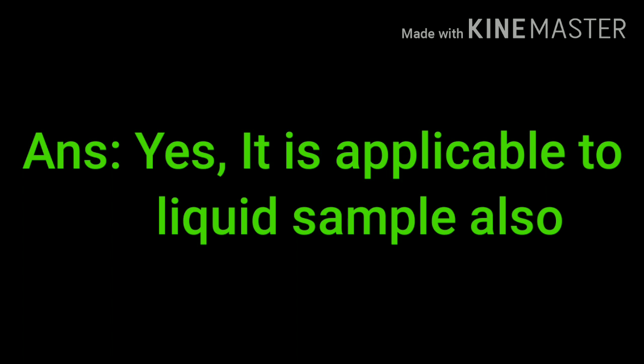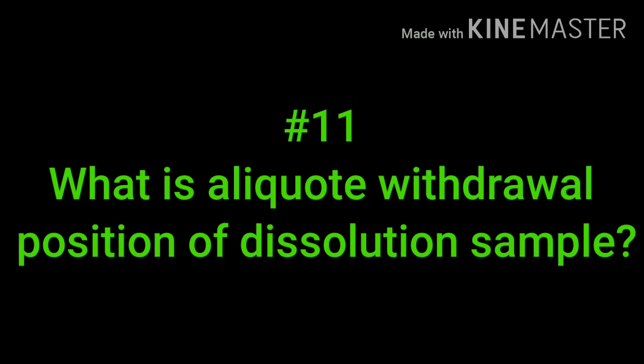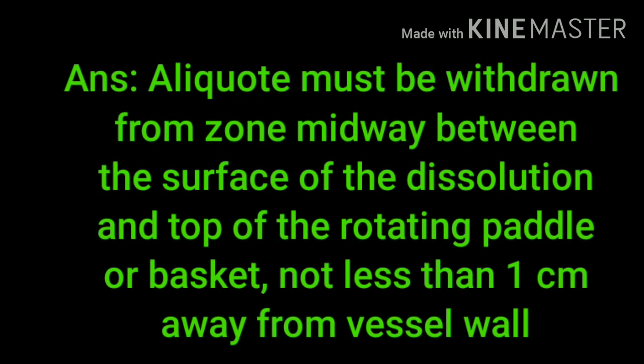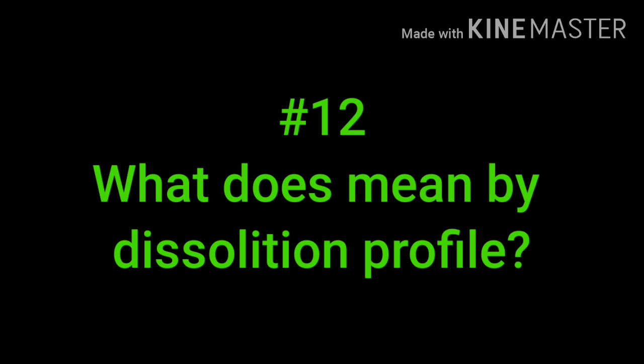What is the correct sample withdrawal position for dissolution? The sample must be withdrawn from a zone midway between the surface of the dissolution medium and the top of the rotating paddle or basket, and not less than one centimeter away from the vessel wall.